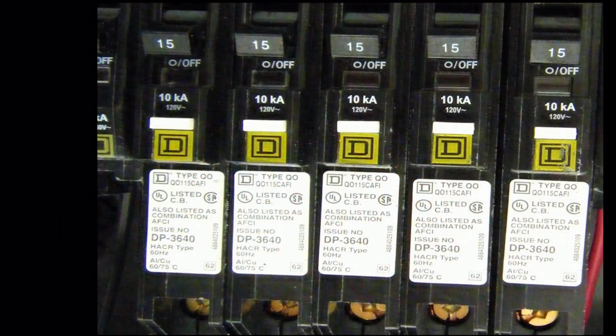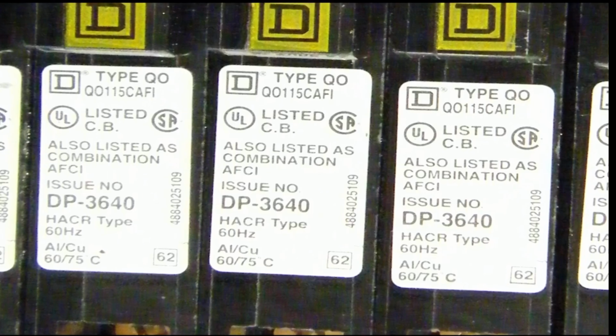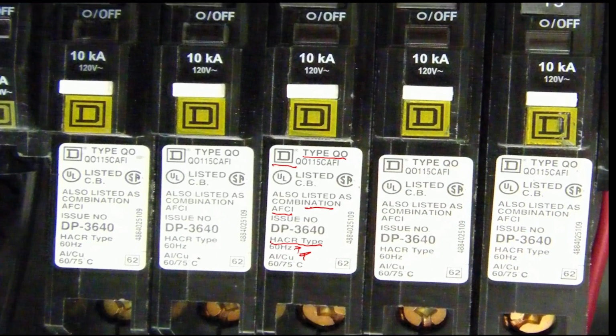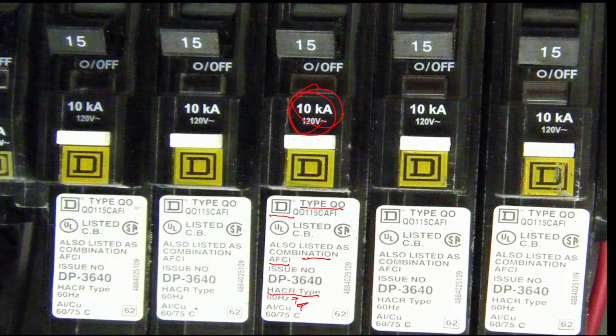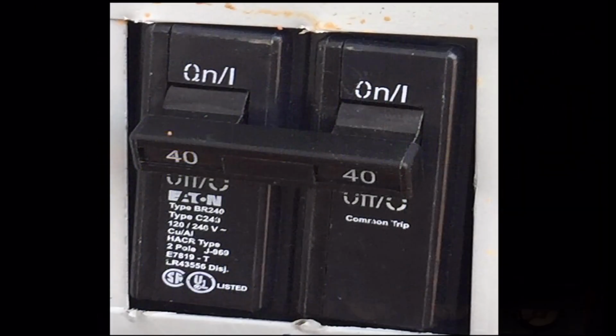Oh, here's some pictures. We love pictures. I'm going to go straight to the iPad. So this is a good example of what's on the face of the device. You have the combination AFCI. You have the type designation from the manufacturer. You have the identification of the manufacturer. You have that this is a HACR type. You have aluminum and copper on the front. You have the frequency on the front. And we've got the interrupting rating and the voltage on the front. We have the ampere rating, and we have on-off.